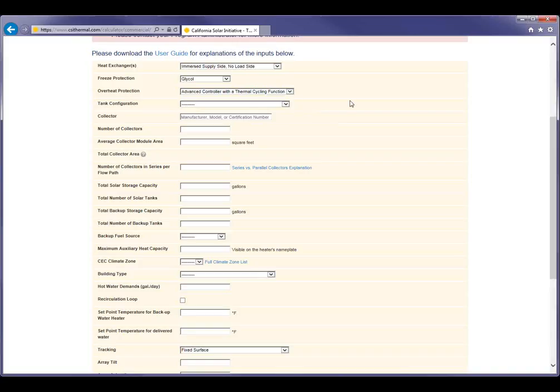Tank configuration, and I should note that all of these inputs are actually described a little bit further in the user's guide as well. Tank configuration really specifies whether there are separate solar storage and auxiliary storage tanks. They can also be one and the same. There are water heaters out there that have heat exchangers in them as well, and for gas tanks, to achieve that, typically it's a specialized gas tank where the burner is introducing heat in the upper portion of the tank, so a heat exchanger can be placed in the bottom and allow solar heat to enter the tank through that heat exchanger. So we really need to identify here whether we have separate tanks for solar storage and auxiliary, whether they're the same tank, or whether we have a tankless water heater or boiler. For this, I'll go ahead and select separate tanks.